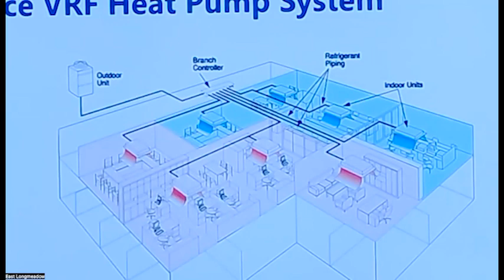Now, an important thing to note here is we're proposing a type of system that would allow for individual classrooms to be in different modes at the same time. So if you're in a shoulder season like spring or fall, and depending on what your exposure is to the sun, you might have one classroom in a zone that's getting sun that might need cooling, and then another classroom on the other side of the wing that might want heating. So this system will be allowed to have both of those classrooms satisfied, one in cooling and one in heating. And the nice thing about the system is that it exchanges energy through the refrigerant that's all piped through this zone, so that it's sharing the heat rejected from one classroom to provide it to another classroom that's looking for heat. So that's an energy efficiency feature. Next slide, please.